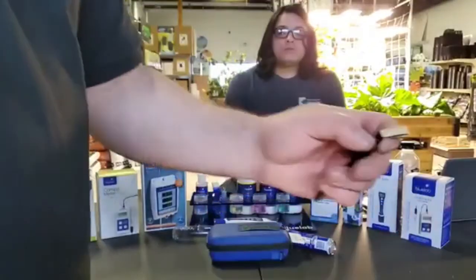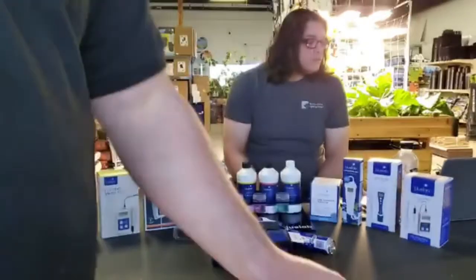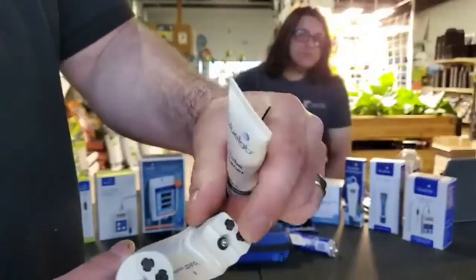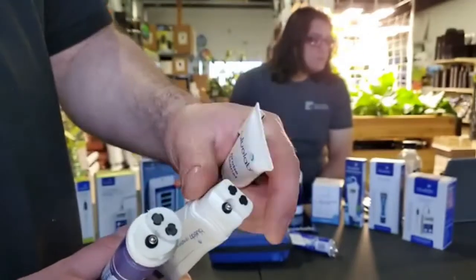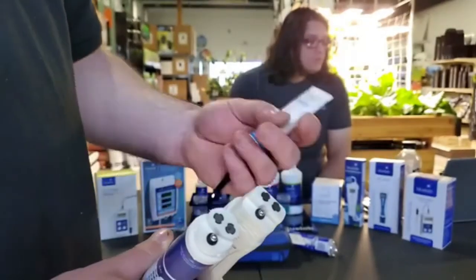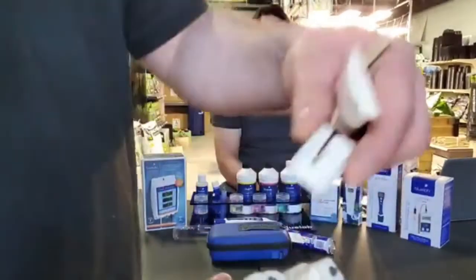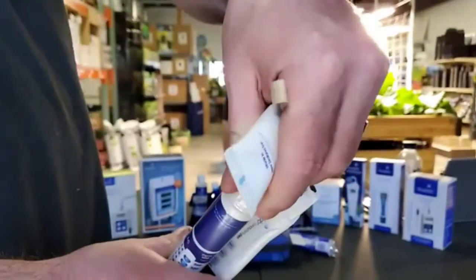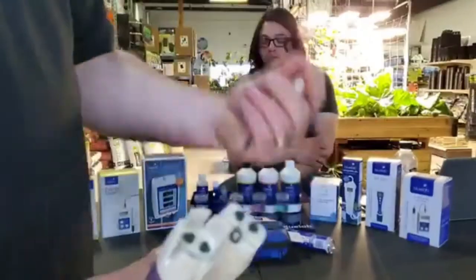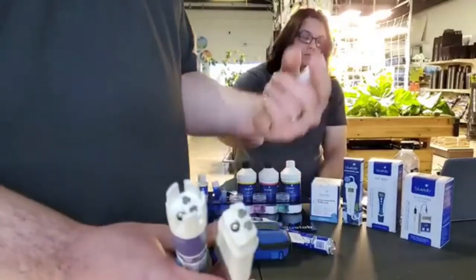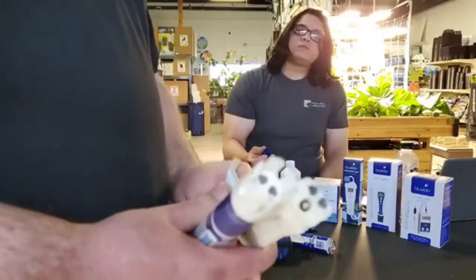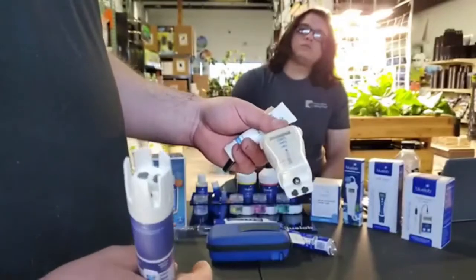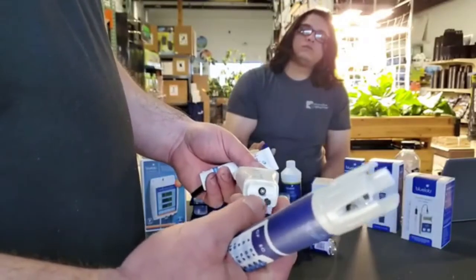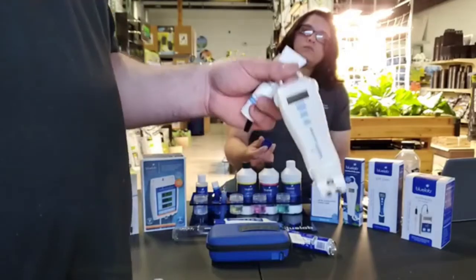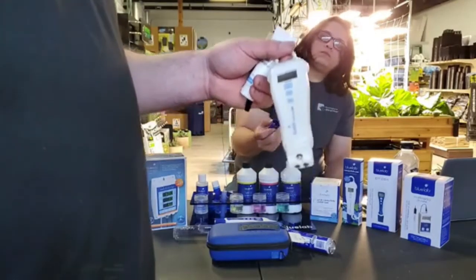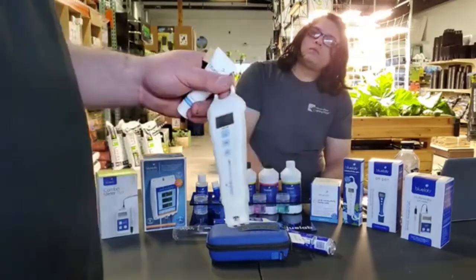And so that's exactly what this is. You've got a little buffer scrubber here, and then this is a mild abrasion solution to go ahead and buff these clean and make sure that they don't have any sort of buildup that's going to be giving you an ineffective reading. And that's really as simple as the maintenance goes. These units are very sturdy. They're calibrated right out of the box directly from the factory. They actually recommend that we don't calibrate them before the customer takes them. And I mean, it's pretty maintenance free. You clean the ends on them every month, and this pen is going to last you a very long time. I've personally used and had one of these pens for over 6 years.